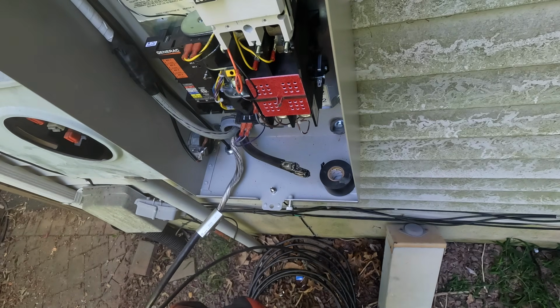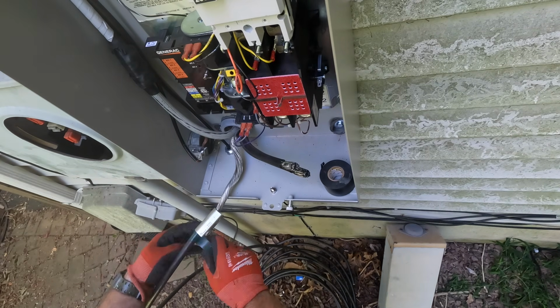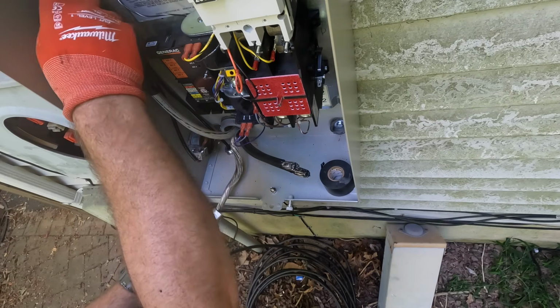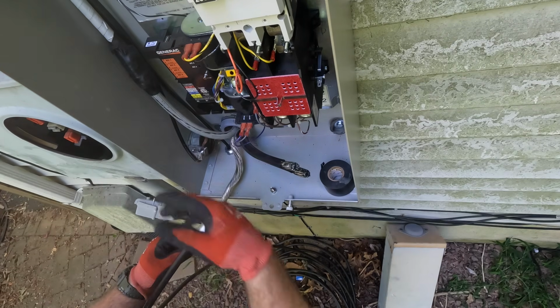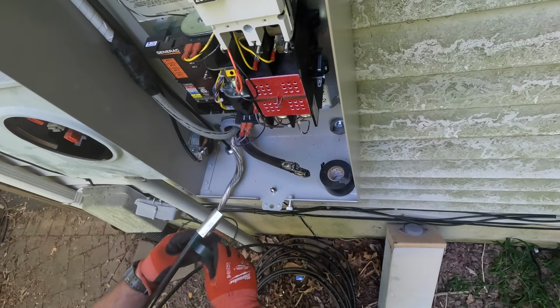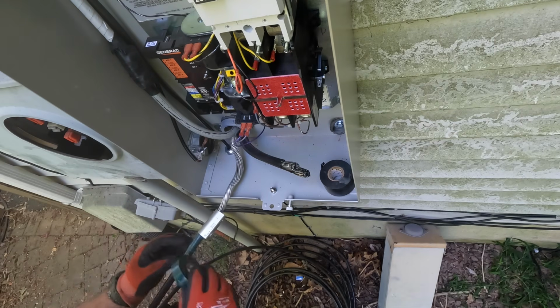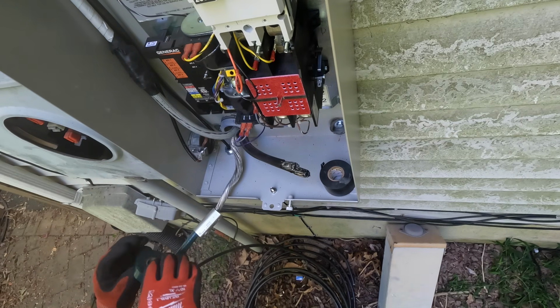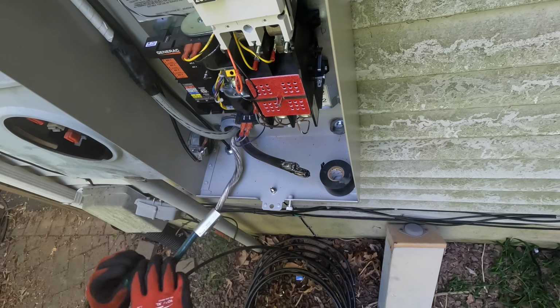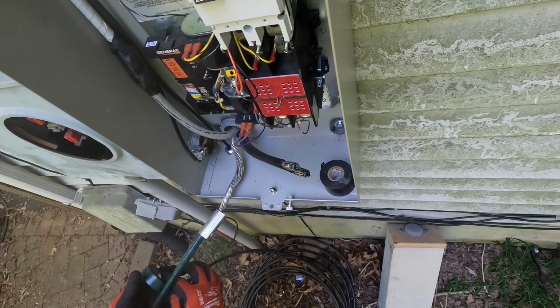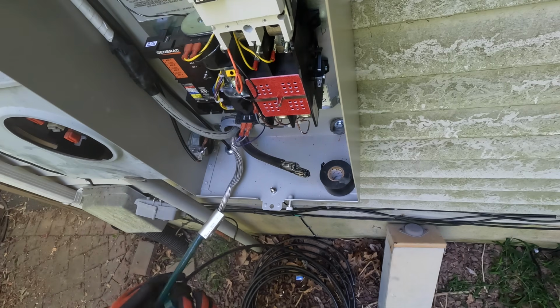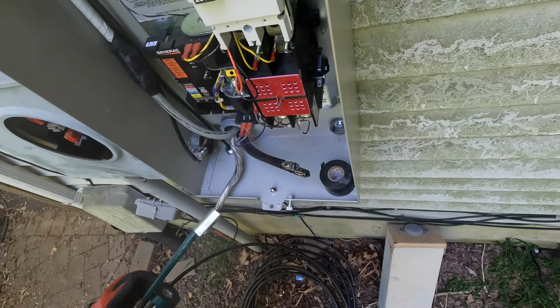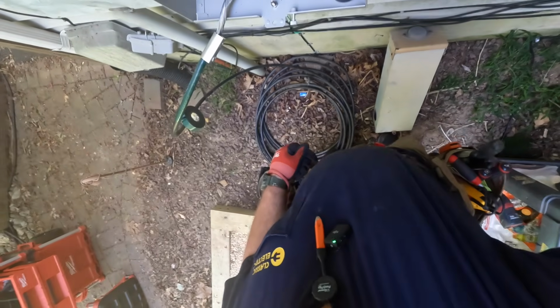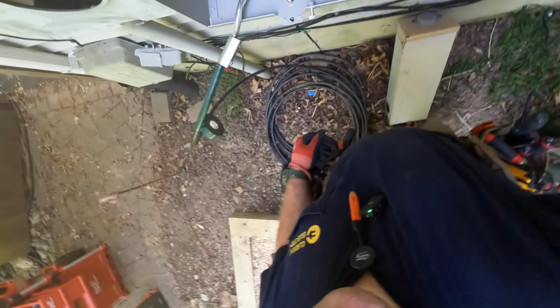Now this one has to be identified because this is the equipment grounding conductor. These black ones that don't need to be green are the grounding electrode conductors. I know that's kind of silly to require for one but not for the other, but they serve two different purposes, as we've been over before on this channel. The equipment grounding conductor removes faults on the system, and the grounding electrode conductor prevents lightning damage, or prevents transient voltages, as Michael always says.